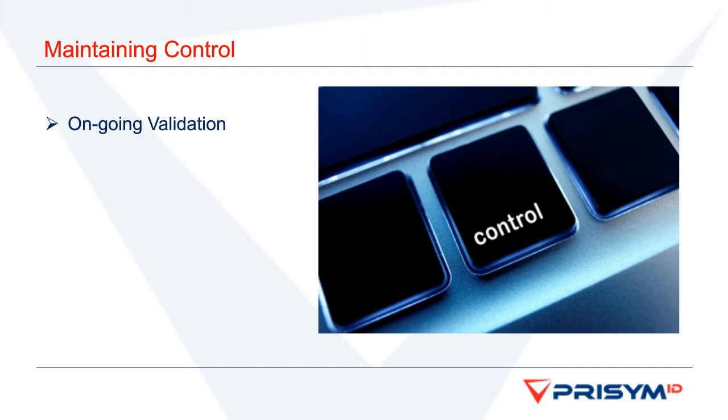There should be a number of documents that you should be able to leverage from your supplier. These will include a release report, which should detail the changes in the release or patch. From this, a gap analysis can be performed using this information and the validation master plan to establish the risk to the control state of the system and the amount of testing that needs to be performed. Patch or release test documents.